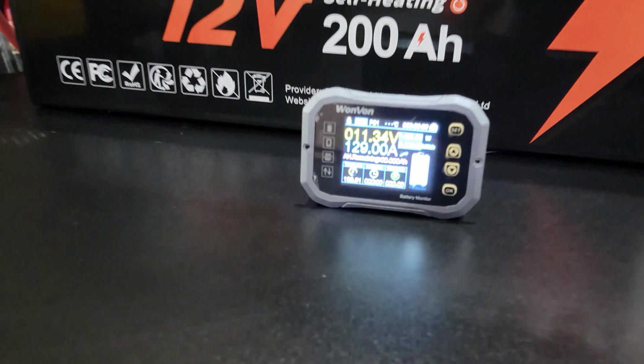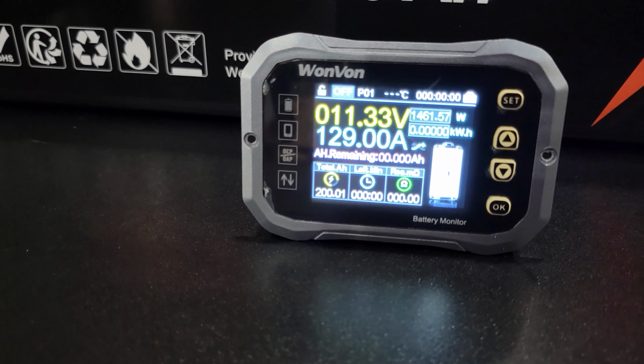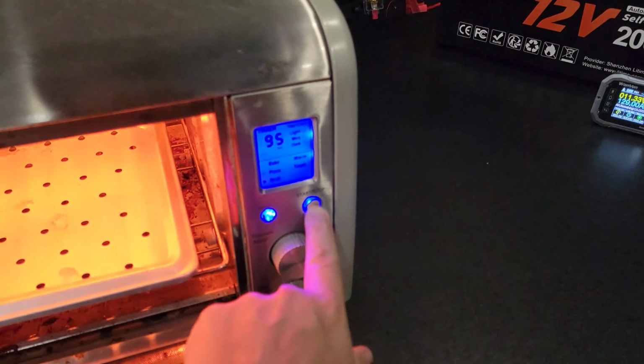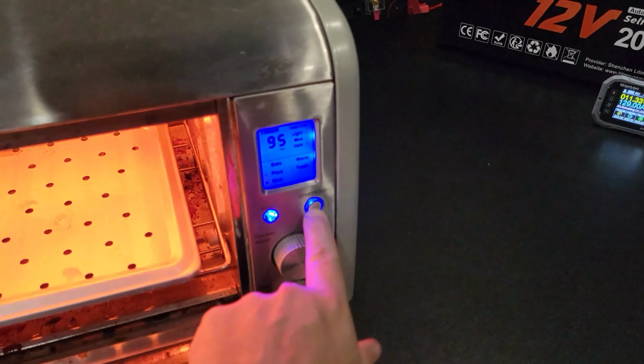Now that we're at 200 amp hours, we just reached it, we want to turn this off because that's pulling too much of a load. So I'm sitting a little bit over 200 amp hours and we have a 200 amp hour battery, so the capacity test passes above and beyond. I believe we could probably squeeze out 204 on this if we go really slow to squeeze it out, but we took it up to 200 amp hours with full power on the oven. So that's a plus. It's a shame the BMS didn't work like I would expect it to.